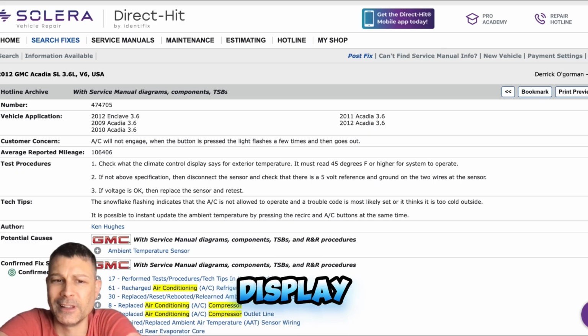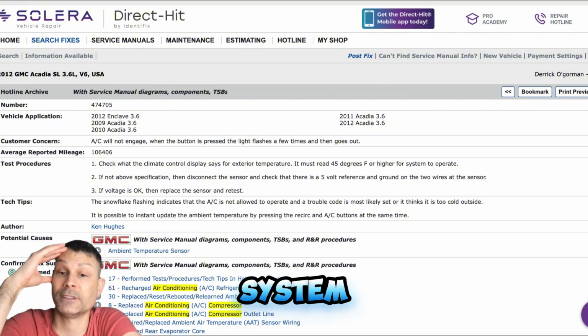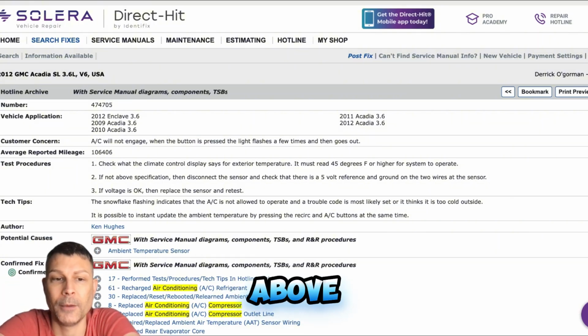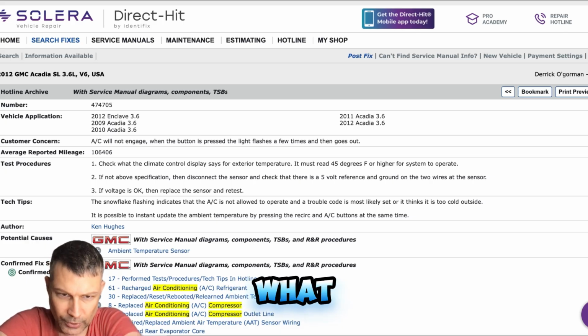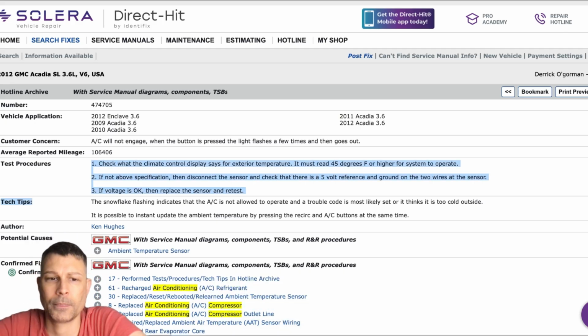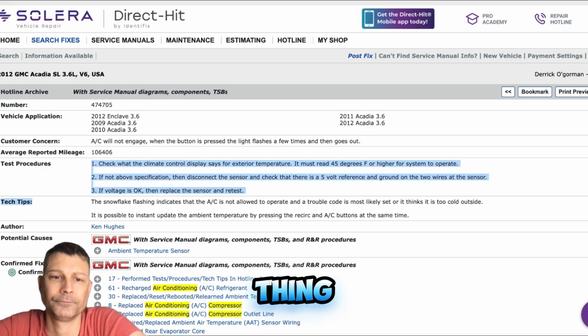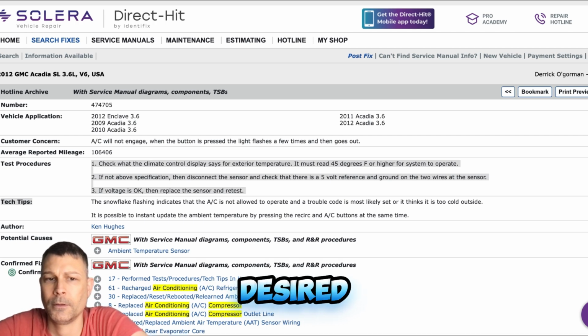That's right. Okay. It says check what the control display says for exterior temperature. It must read 45 degrees Fahrenheit or higher for the system to operate. If not above specification, then disconnect the sensor and check for a 5-volt reference at the ground of your sensor. So what is your climate control display for exterior temperature? I've got to find it again. Let me go back to my sensors. Now, one thing I'm looking at on the evap temp sensor, it says 93, and then evap temp sensor desired 183. So there's a big discrepancy.